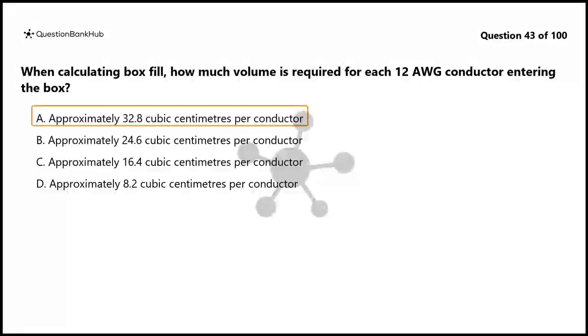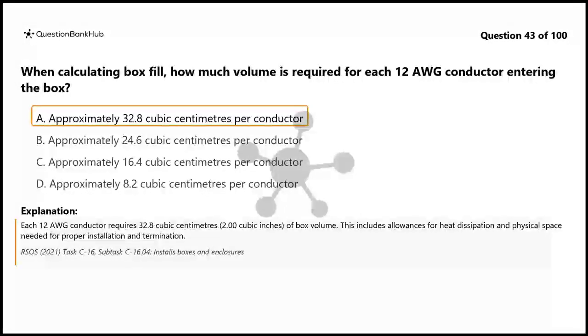The correct answer is A. Approximately 32.8 cubic centimeters per conductor. Each 12 AWG conductor requires 32.8 cubic centimeters, 2.00 cubic inches, of box volume. This includes allowances for heat dissipation and physical space needed for proper installation and termination.